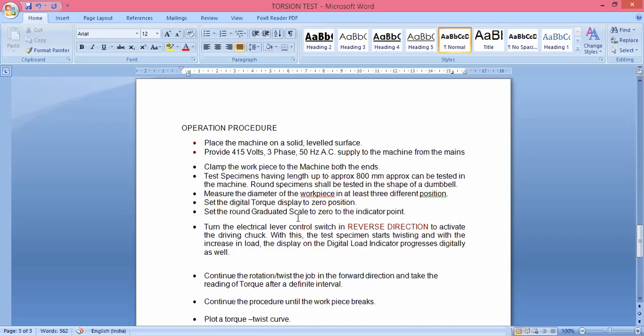Now we rotate the graduated disc, and the job moves in the forward direction. We take the measurement of the torque after a definite interval. So after say 5 minutes or 10 minutes, we take an interval and see, for each degree of rotation, how much load is displayed on the display device. Now continue the procedure like this. You may see maybe two, three, even seven twists for the block before it breaks. You continue the machine until it breaks.